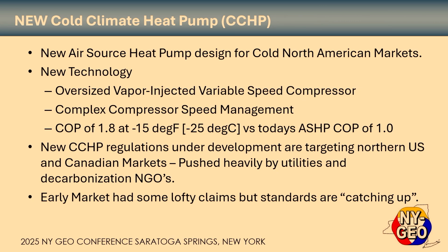The new cold climate heat pump regulations are under development, meaning the standards; AHRI 210-240 has been modified here recently. So you're starting to see some more things about the 5-degree temperature is now being measured and certified and that sort of thing. And then there's also a new standard that's going to replace 210-240. I'll go into that here in a second. That will be more heavily into the cold climate heat pump.